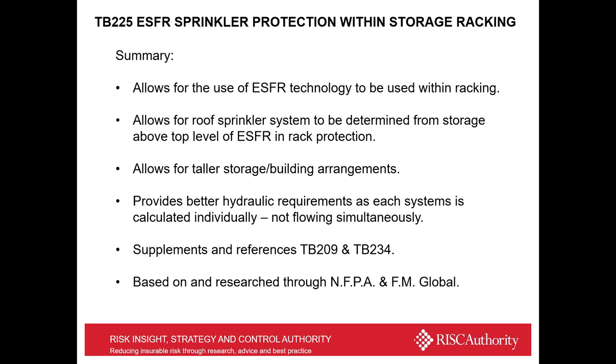So in summary, TB225 allows for the use of ESFR technology within racking. It allows for the roof system to be determined from the storage level above the top level of ESFR. So like I say, it can be an ESFR sprinkler system above that top level of in-racks, or it can be control mode based on a density over an area under TB234. It allows for taller storage building arrangements. It provides better hydraulic requirements as each system is calculated individually. That's another benefit of the ESFR in-racks.